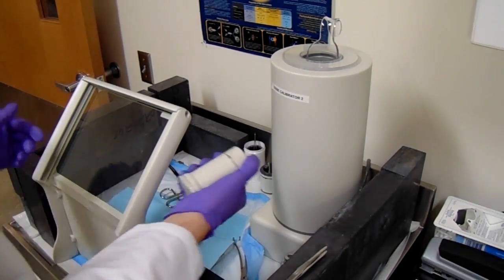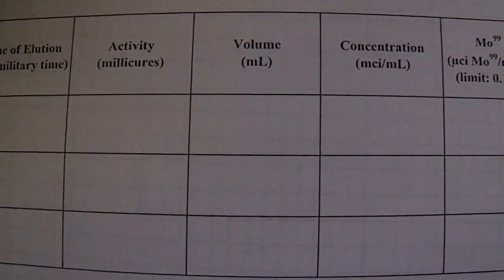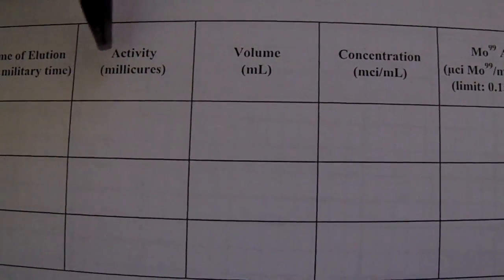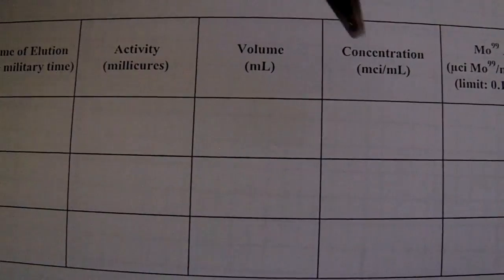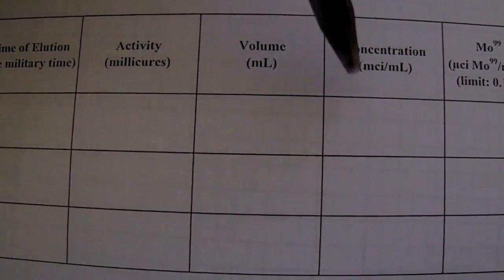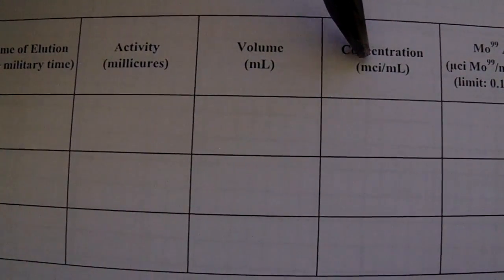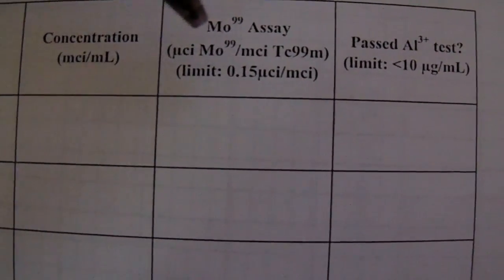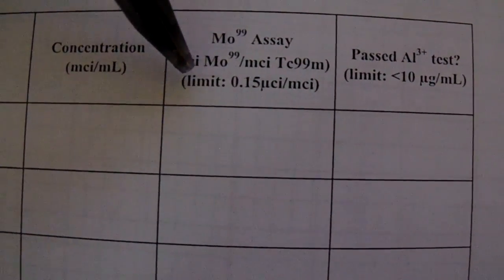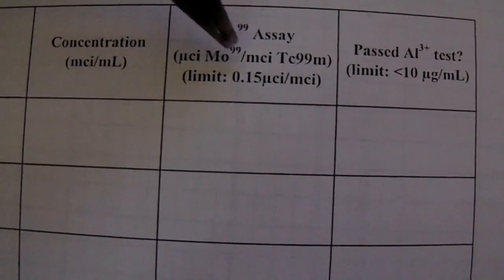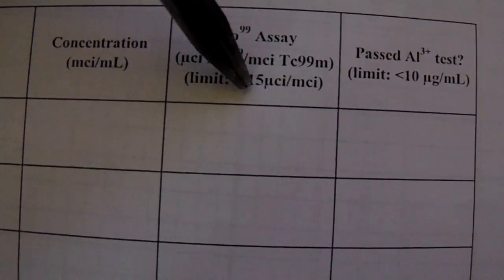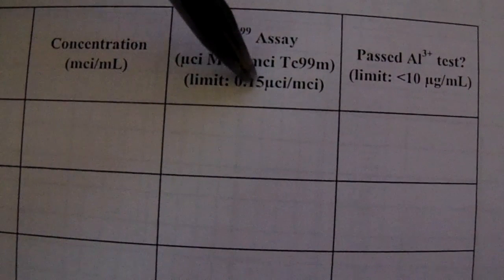Now, in order to get the concentration of your eluate, you need to take the activity in millicuries and divide it by the volume of the elution to get your concentration. Now, you're going to divide your moly assay by the amount of activity you had in technetium. And as long as you have less than 0.15 microcuries of molybdenum per millicurie of technetium, that means the amount of molybdenum in your elution is safe to inject with.